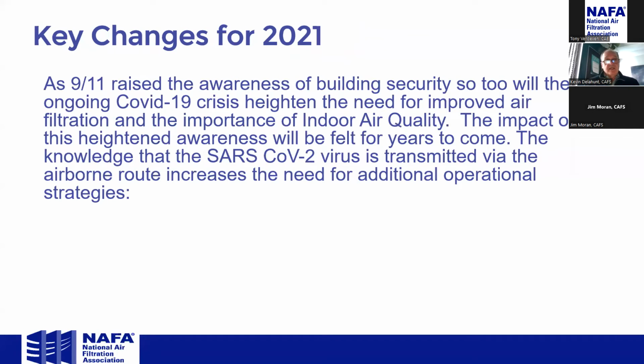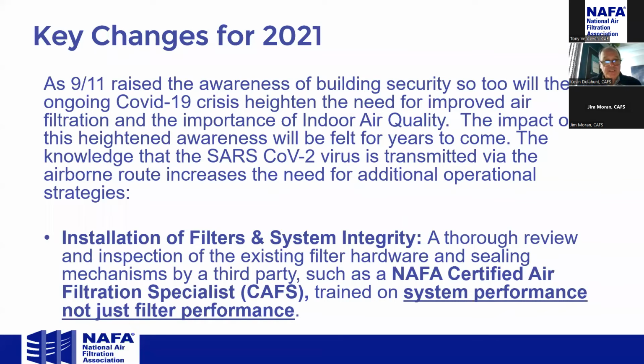Just a comment: as 9/11 raised awareness for the building security industry, so too has the ongoing COVID-19 crisis heightened the need for improved air filtration and the importance of indoor air quality. The impact of this heightened awareness will be felt for years to come. The knowledge that the SARS-CoV-2 virus is transmitted via the airborne route increased the need for additional operational strategies. The first strategy is installation of filters and system integrity: a thorough review and inspection of the existing filter hardware and sealing mechanisms by a third party, such as a NAFA certified air filtration specialist, trained on system performance, not just filter performance. So we look at the whole structure, not just the filter, but the filter hardware and what the filter sits in.